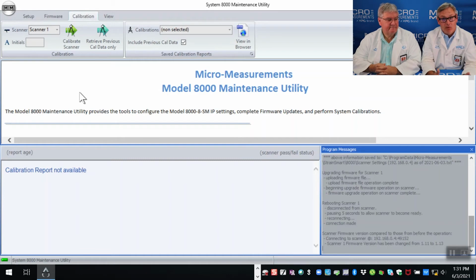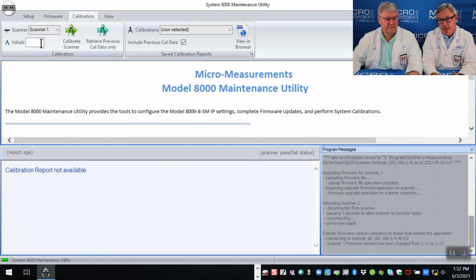of different VCal cards that they use to cycle through multiple scanners. You could have 2 VCal cards in one scanner, or you could have multiple scanners and use one VCal card to calibrate all of them. You get to choose how you want to handle your calibration, but it really eliminates downtime for customers that need to maintain that traceability and that calibration with their equipment.